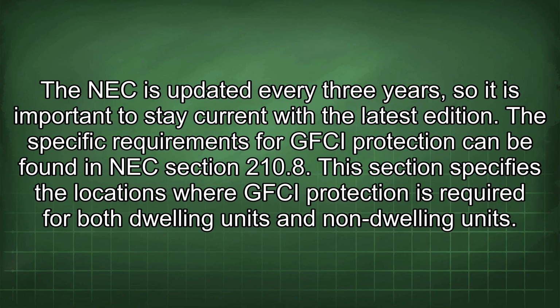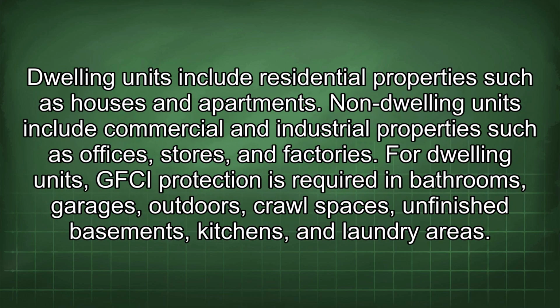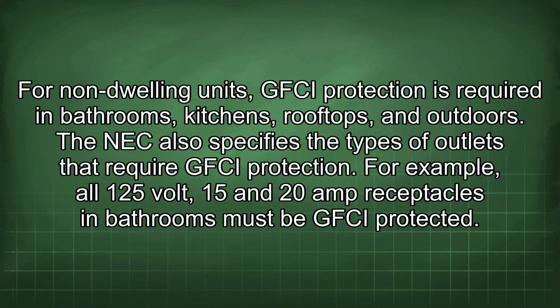This section specifies the locations where GFCI protection is required for both dwelling units and non-dwelling units. Dwelling units include residential properties such as houses and apartments. Non-dwelling units include commercial and industrial properties such as offices, stores, and factories. For dwelling units, GFCI protection is required in bathrooms, garages, outdoors, crawl spaces, unfinished basements, kitchens, and laundry areas. For non-dwelling units, GFCI protection is required in bathrooms, kitchens, rooftops, and outdoors.